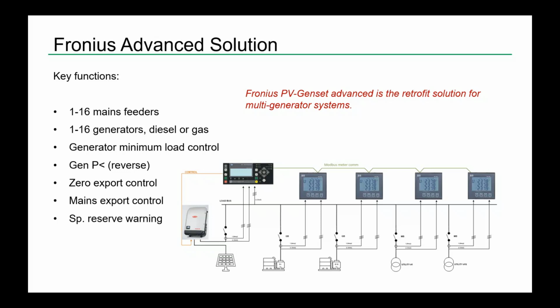We measure the power sources. You can see on the sketch that we have digital power meters, one on each power source, and this also means we always know how much we import, export, or how much power the generator is producing. This way we can handle the generator minimum load control. An additional advantage is, of course, generator power protection, reverse power protection, so you don't need to buy additional reverse power protection relays if you have this system.